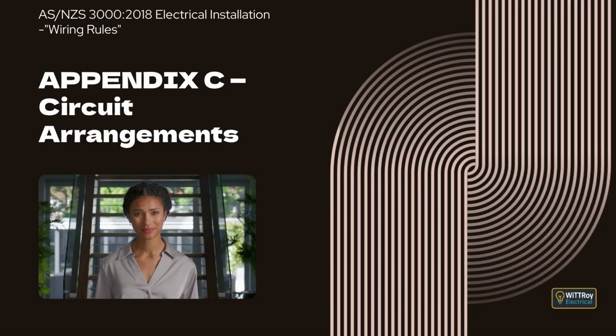Clause C 2.4.2.2, Example 5. This example explains how to determine the maximum demand of the heaviest loaded phase for a factory installation supplied by three-phase. Lighting, socket outlets, air conditioning, motors, welding equipment, water heating, and specialized machinery are assessed. The method shows how full load current, reduced load for additional machines, and duty cycle effects are taken into account. The loads are balanced across phases as far as practicable, and the maximum demand is taken from the most heavily loaded phase.